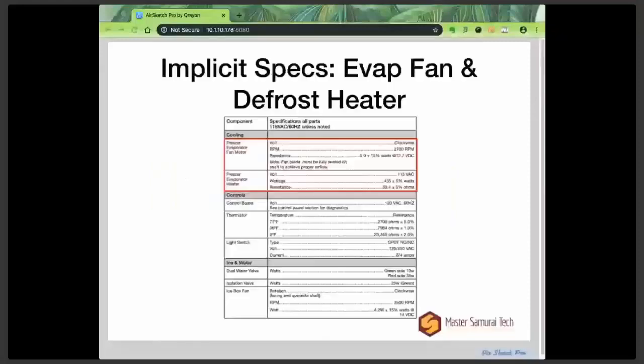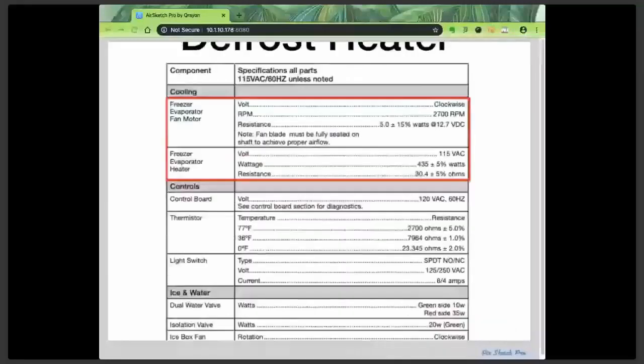Again, this is from that same Whirlpool tech sheet showing specifications. Let's look first at the defrost circuit, what they're calling out as the freezer evaporator heater. So they give resistance, 30.4 ohms, plus or minus 5% as your tolerance on that.